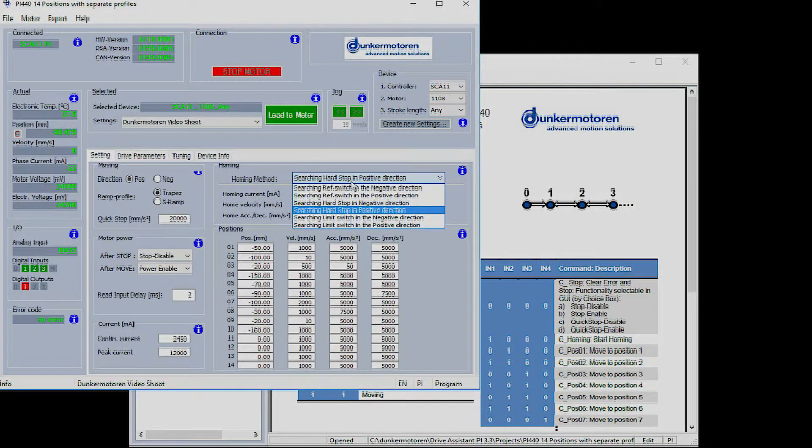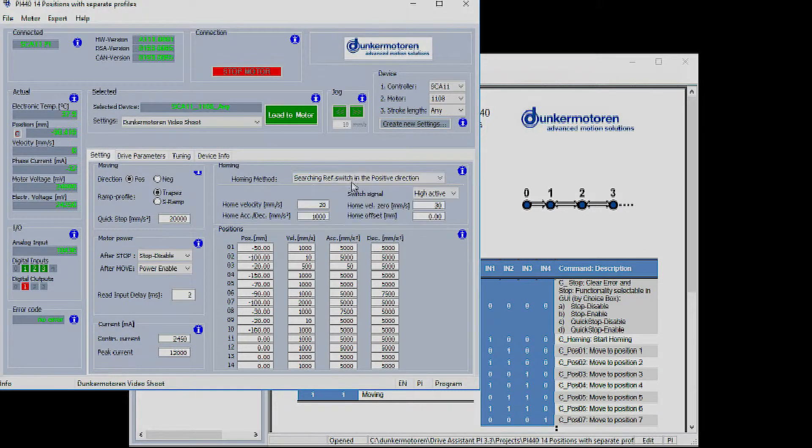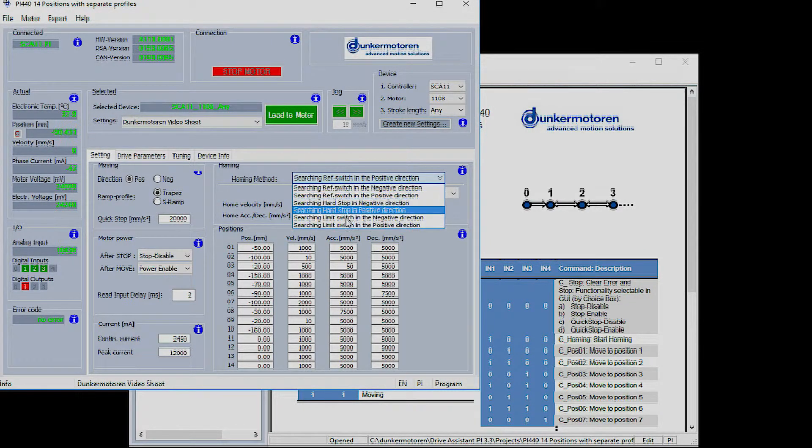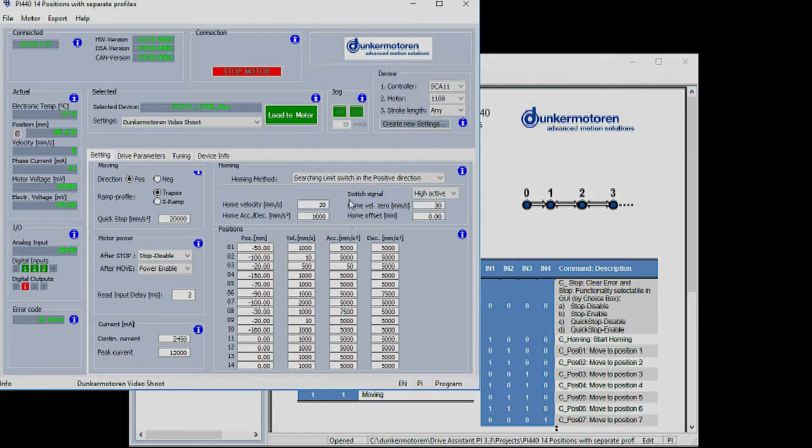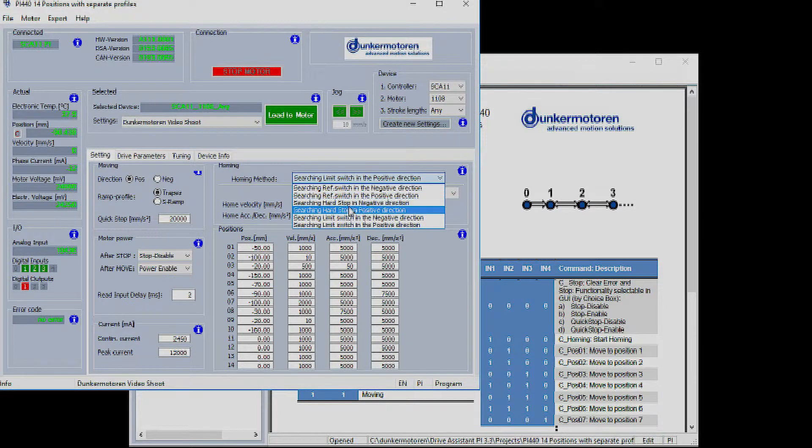If homing to a limit switch the motor will always back away from the limit switch at a much lower speed looking for the edge of the switch for final home position.